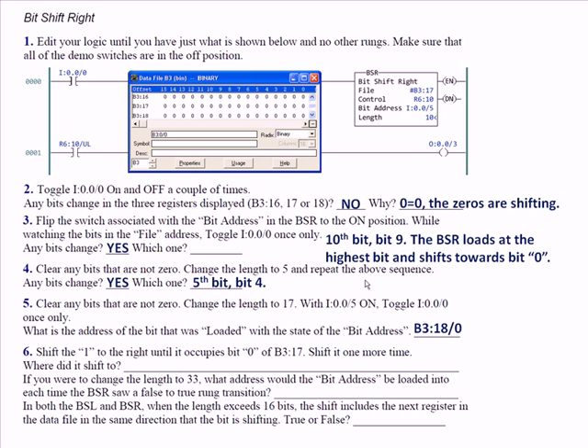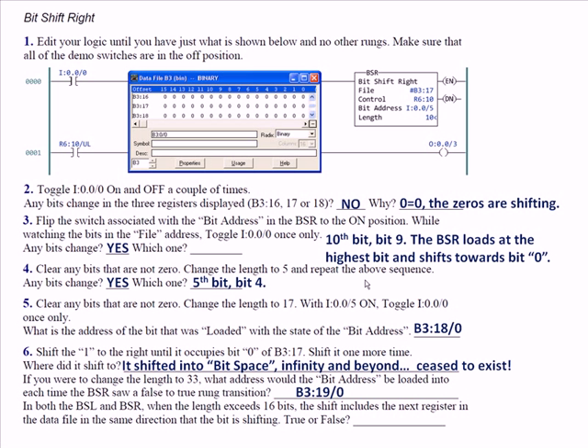Shift the 1 to the right until it occupies bit 0 of B3:17 — that's the last position. Shift it one more time and it shifts into bit space: infinity and beyond, ceasing to exist, the bottomless bit basket. If you were to change the length to 33, the bit address would be loaded into B3:19 bit 0 — the highest bit in the file. Those are the exact same 33 bits worked with using BSL; the difference is you load the highest instead of the lowest and shift in the opposite direction. For both BSL and BSR, when the length exceeds 16 bits, the shift includes the next register in the data file in the same direction the bit is shifting — true.